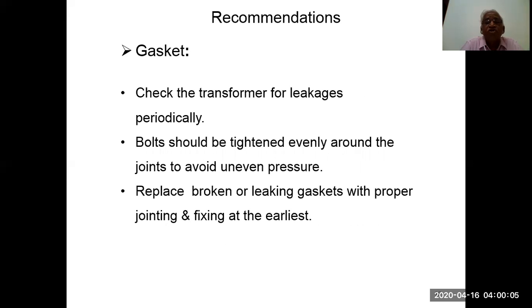Gasket. Check the transformer for leakages periodically. Bolts should be tightened evenly around the joints to avoid uneven pressure. Replace broken or leaking gaskets with proper jointing and fixing at the earliest.